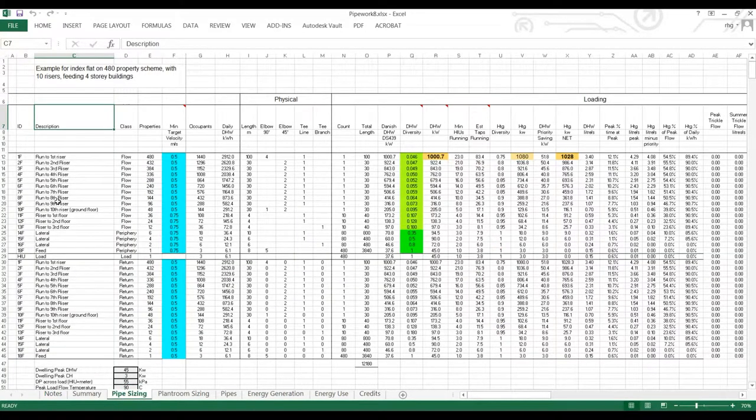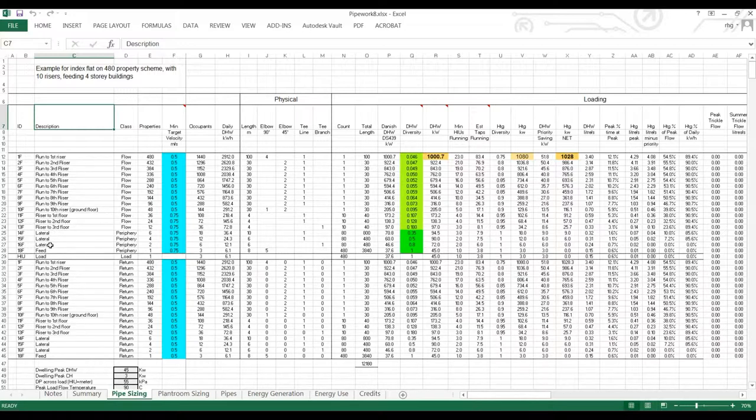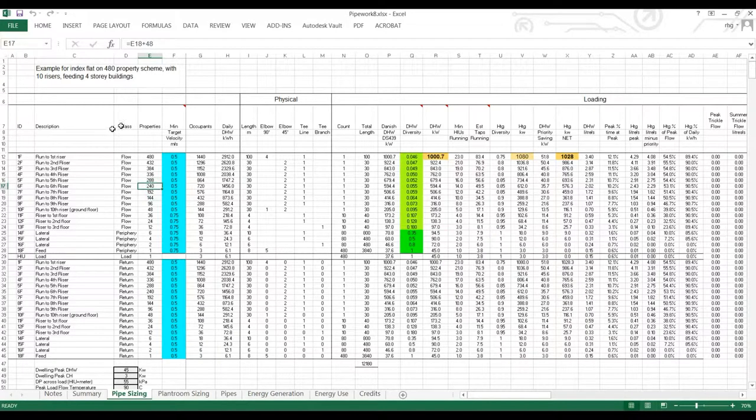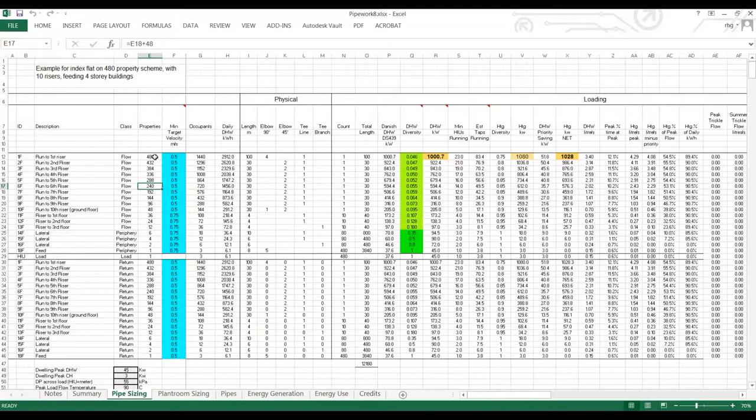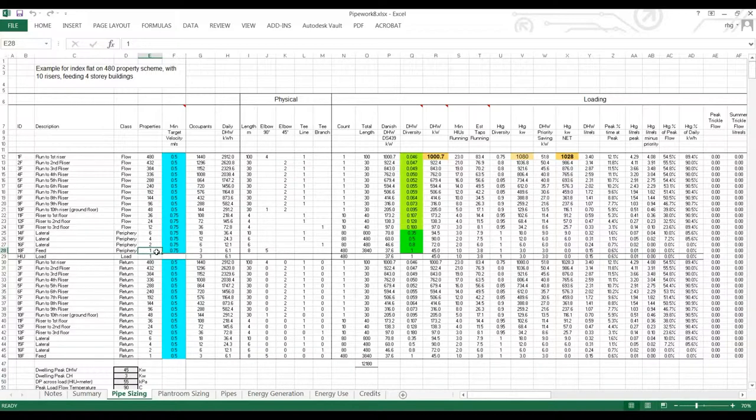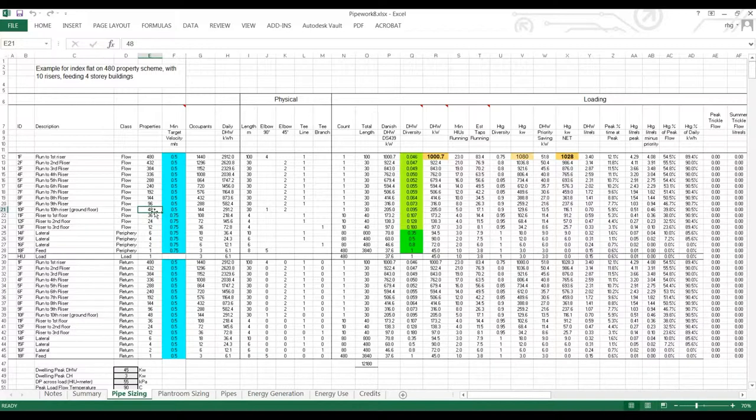Now these represent the pipes from the plant room past the blocks to the last property on the site. So that's the run past the risers, up the last riser, along the lateral into the property. In this column we have the total number of properties the pipe is feeding. So the pipe coming out of the plant room is feeding 480 properties. The pipe into each property is feeding a single property and each riser is feeding 48 properties.